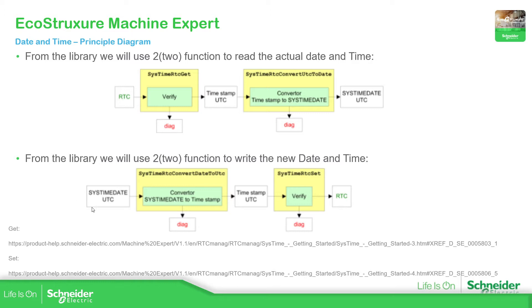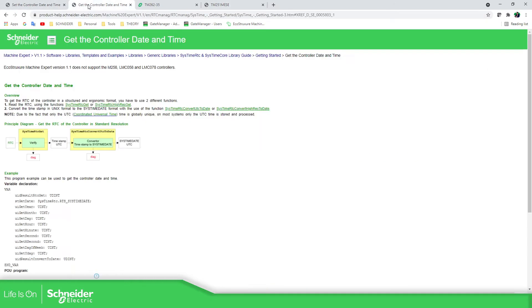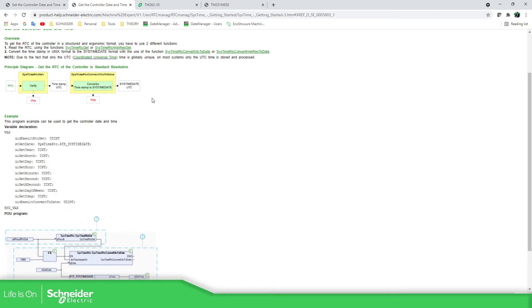To write, we need to use a variable with the SysTimeDate structure. In here we have the new RTC values. We use the converter from date to UTC to receive the UTC timestamp, and then we use SysTimeRTC Set to write into the controller. If we go to this link - the online help for the controller - we have the Get function block, and this is where I took the pictures from.